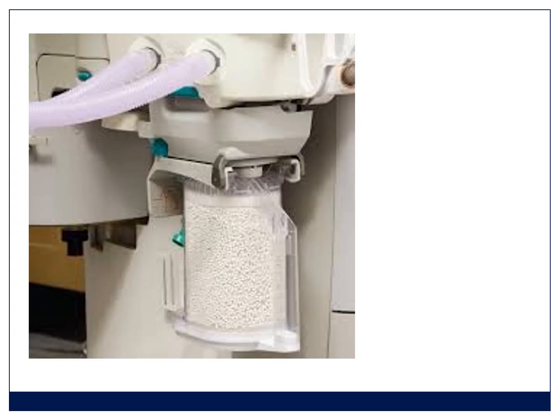Then you need to check your soda lime, your carbon dioxide absorber. It must be securely in place. Again, depending on the system you've got, these often are a cause of leak. They don't sit nicely, or some of that soda lime gets into the seal. It should be nice and white.